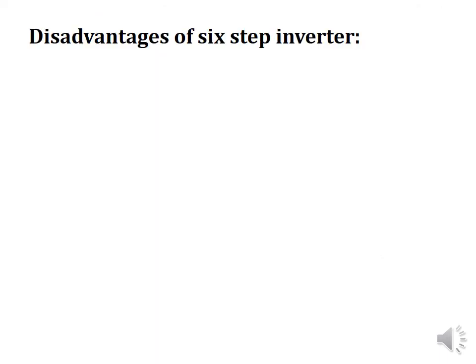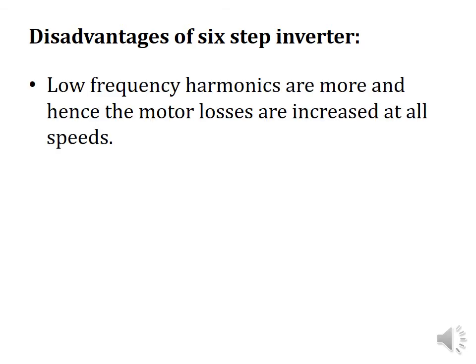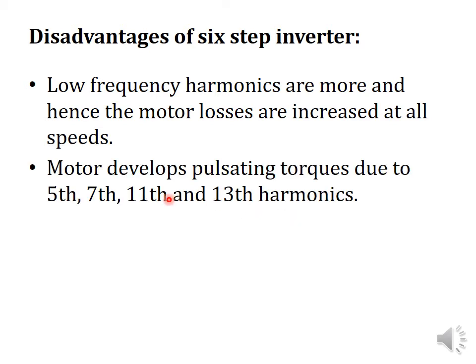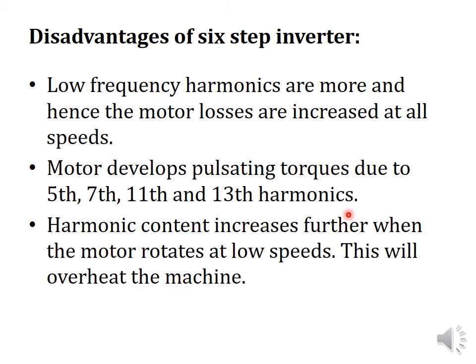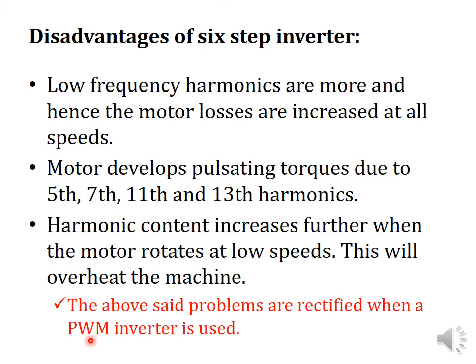The disadvantages of a six-step inverter: first, the low-frequency harmonics are more, and hence the motor losses are increased at all speeds. The motor develops pulsating torques due to the 5th, 7th, 11th, and 13th harmonics. Additionally, the harmonic content increases further when the motor rotates at low speeds, which will overheat the machine. These are the major disadvantages of using a six-step or stepped wave inverter.